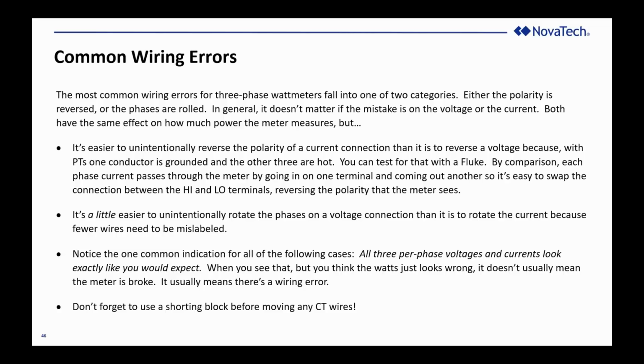I type in the voltage and the current and the phase angles, and it tells me what the per phase watts are, what the total watts are, and I can use that to dial in a 180-degree phase shift if someone wants to simulate what the results would be if he inverted the polarity of one of the connections, unintentionally, obviously, it's a wiring error, or if he rolls the phases. Now, once you recognize that, first of all, these wiring errors are fairly common, and secondly, that they're easy to simulate, but they're hard to remember. Having this calculator in your hip pocket when you see something that you don't expect might be very handy. And tabulating the results might be a nice check if I'm connecting a wattmeter in a substation and I see a pattern that isn't obvious what it indicates, how to correct it easily.